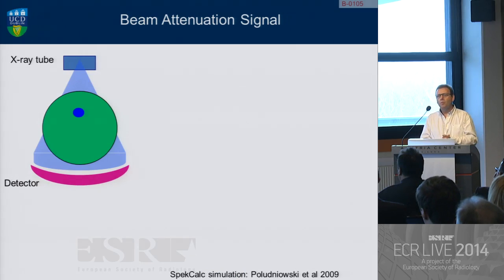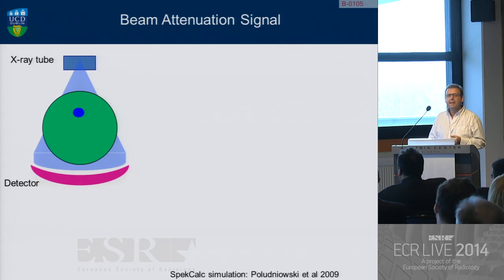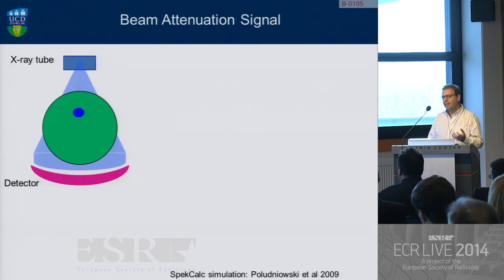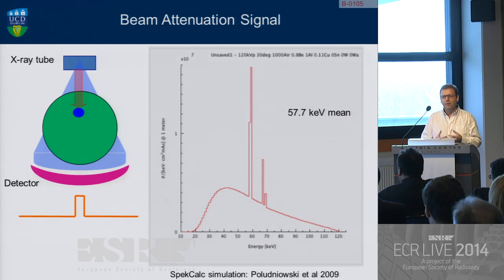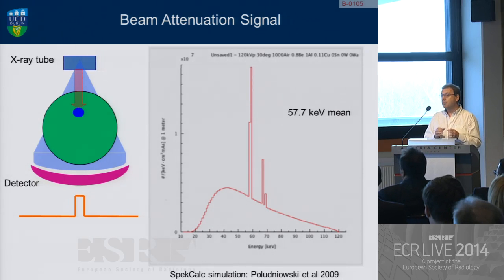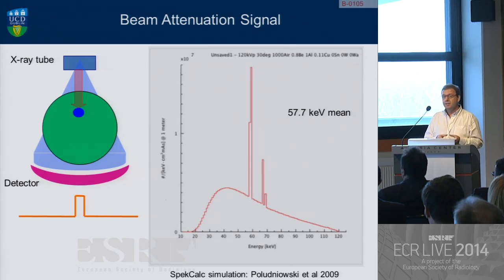We all know beam hardening. In this simulation, I'm going to use the SpekCalc algorithm to simulate the artifact, and then I'll talk you through the actual research. Basically, we have a beam spectrum that actually travels through the scan field. And if we stick a metal rod in the beam path, we get an attenuation signal recorded from that piece of metal.